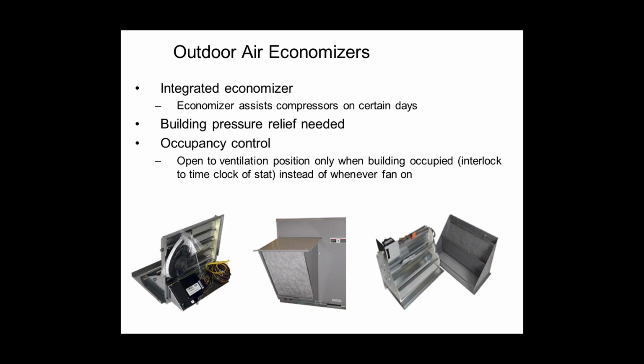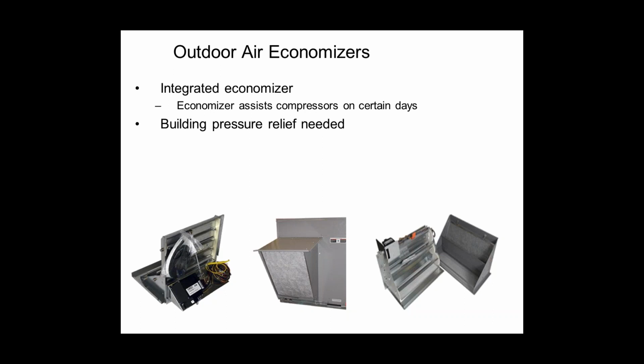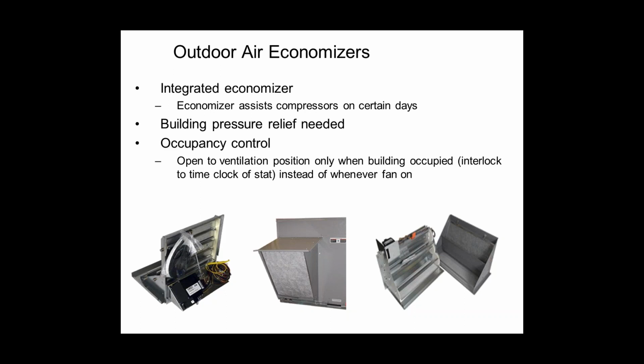There are numerous ways that we can do that. We could do it with a barometric relief damper. We could do it with a motorized damper and powered exhaust fan. We can do it with an external exhaust fan that's outside of the air handler or rooftop. We could do it with a dual stage relief path. There's lots of ways we can do it. We could talk all about that stuff if you guys want to later. But just make sure you have a plan on getting air back out of the building because they're going to suck a lot of air in.